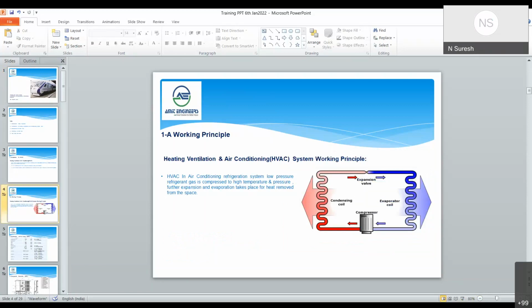Yes, sir. This is the basic HVAC refrigeration system. Any vapor compression system will have these basic components: compressor, condenser, expansion device, and evaporator coil. The compressor compresses the low pressure refrigerant to high pressure refrigerant. That is how the temperature rises and the pressure also rises. To bring down the temperature and pressure, it is passed through the condenser, where axial fans are used to reject the heat. Once the heat is rejected, the vapor converts into a semi-vapor condition.